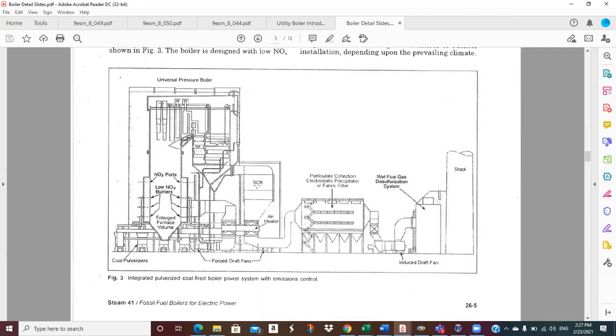So there are optimal temperature ranges for these things to operate. And see, this is before the air heater, so this is like 700-800 degrees Fahrenheit. That's where they can do the best NOx capture, so they put it in there. And then they go through the air heater, and then through the precipitator. So we get our particulates before the ID fan, which is a really good idea. And then we go through the wet flue gas desulfurization system. So we're taking out NOx, particulate, and sulfur compounds here.